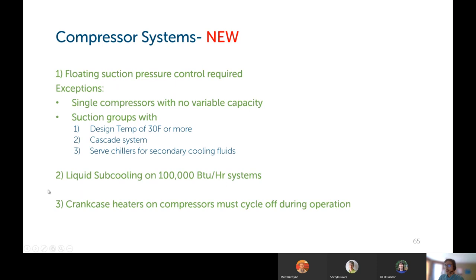Another requirement is that you need to have liquid subcooling on 100,000 BTU per hour or greater systems, and crankcase heaters on compressors must cycle off when the compressors are operating.